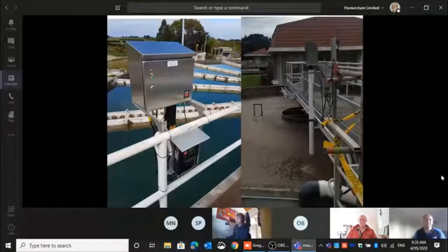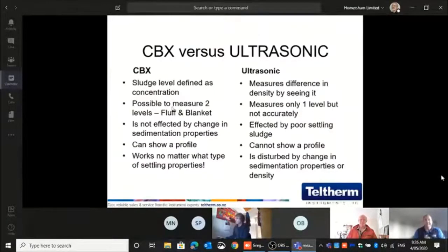Now, what's the difference against ultrasonics? First of all, we define it as a concentration, the sludge level, while ultrasonics looks at densities. We give you 2 levels, fluff and blanket, while ultrasonic gives you 1. Not very accurate, but it gives you 1 level. We are not affected by sedimentation properties, while with ultrasonic, if you have poor settling sludge, it will get into trouble very quickly. We can also show you a profile.